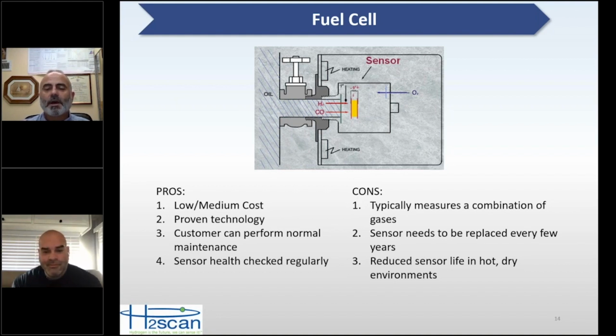So the cons, typically, most of the ones out there today measure a combination of gases, and so that might be a good thing, but you have to do a calculation based on your oil sample to see if it is really reading kind of what you would expect it to. The sensors need to be replaced every few years, whether that's 1 year or 5 years, I'm not sure how long those are lasting these days, but typically you're going to replace the sensor 2 or 3 times in a monitor's life.